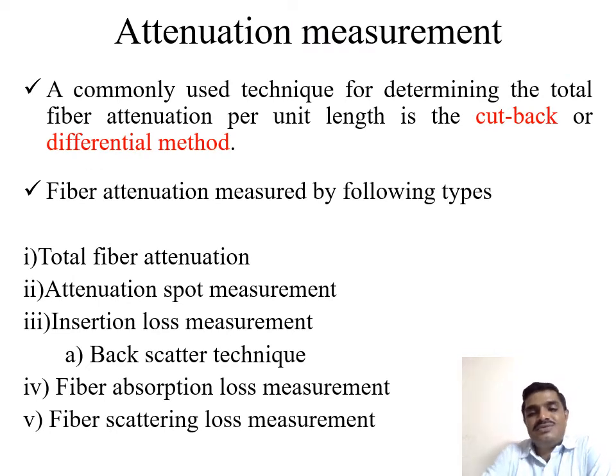Let us discuss the attenuation measurement unit. A commonly used technique for determining the total fiber attenuation per unit length is the cut-back or differential method. Fiber attenuation is measured using the following steps.